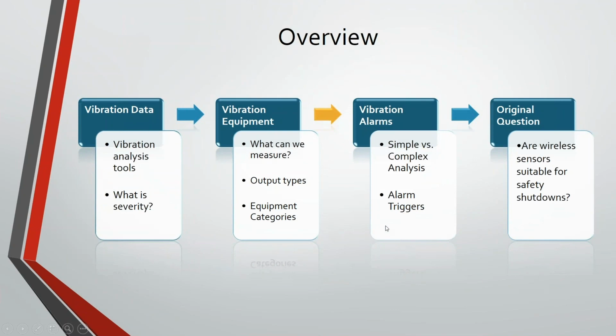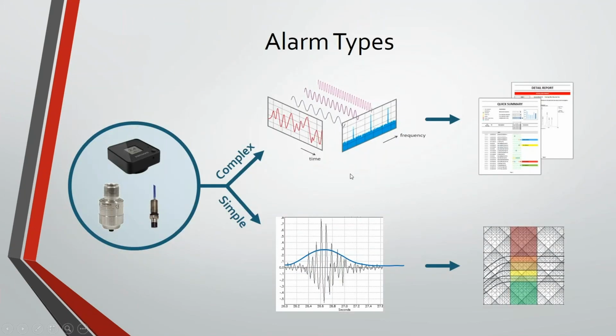So given all of that, one last thing we want to consider is, how do we want to be alerted? And that has a lot to do with what we want our alarms to tell us. And in some cases, if we keep the data complex, we're able to go up in the cloud and we can get really advanced alarming capabilities that are specific to frequencies. And if any little tiny thing changes in the machine, we can be alerted to that. Whereas if we're going to simplify the data and look at the overall level and use severity, we're relying on industry standards to tell us that, in most cases, based on most failure modes, we're going to be able to shut this machine down in time for you to save some money for your facility and protect everybody, right? So depending on what you want to do, that would help you decide which direction you want to go with your data.